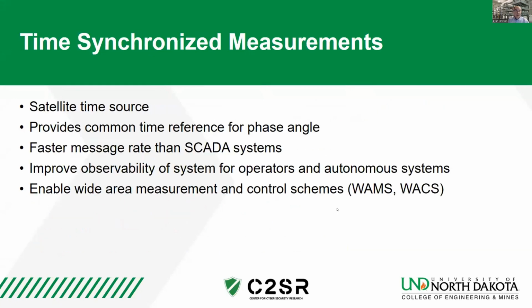To improve visibility of the system, people have started using time-synchronized measurements. Most SCADA systems are set up assuming there's no common clock across substations, so an optimization calculation is done to get the state of the system, which is over-measured. Time-synchronized measurements can enhance that, and in theory make a direct state measurement possible. Very few utilities have enough penetration of these time-synchronized measurements, or reliable enough communication systems, to support that. So most use time-synchronized measurements for other purposes in controlling the system, rather than for some of the central parts of system control.